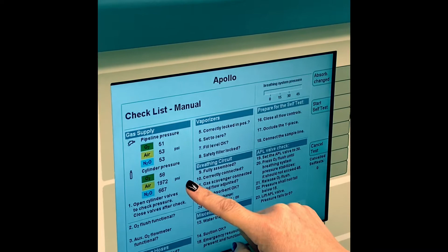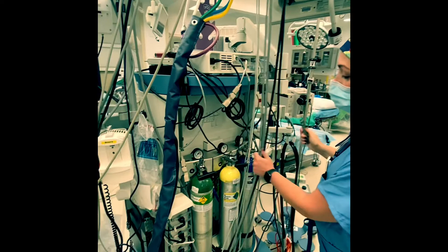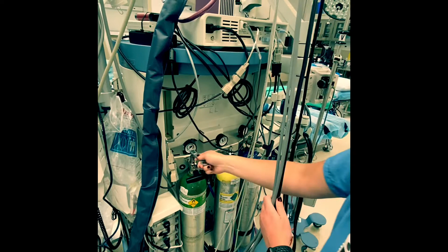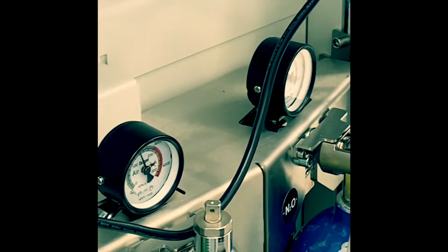And when you're doing your machine check, you're always going to crack your tanks, which are going to be behind the actual ventilator. Every ventilator machine will have a key. You take the key, which is found sitting on the top of one of these 3 cylinders. You're going to crack open, and it raises your pressure here, and then you're going to close it back. And you're going to do that with all 3 of your tanks back here.